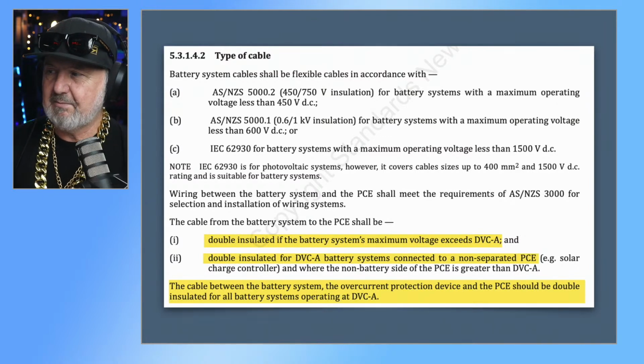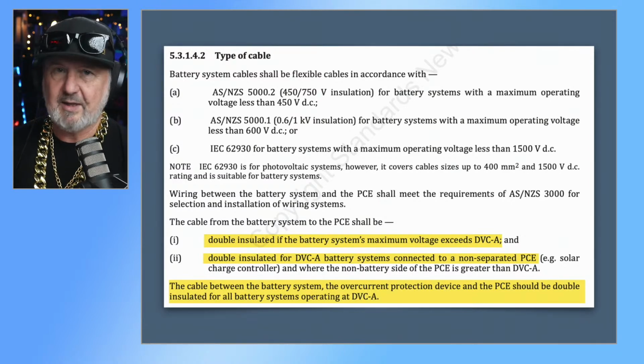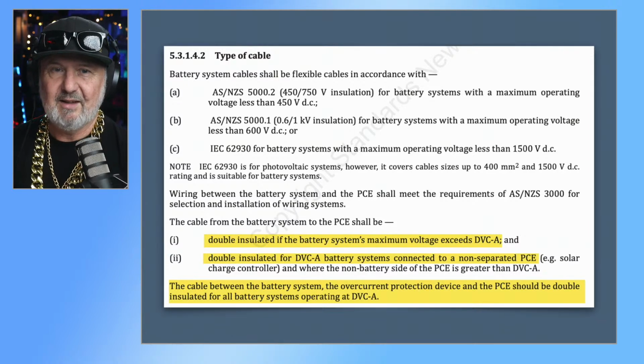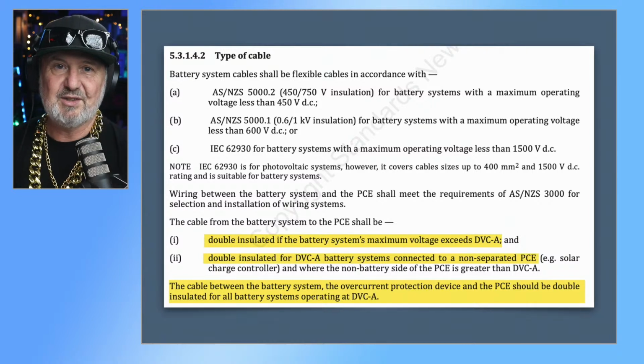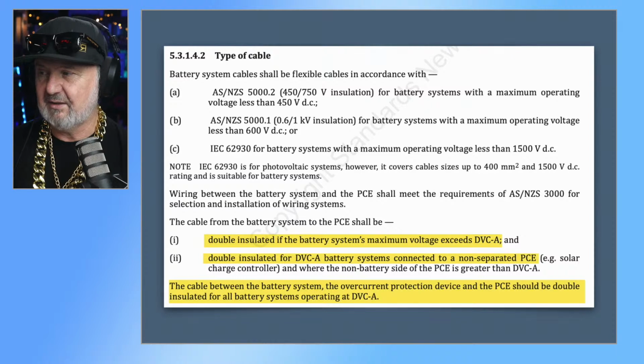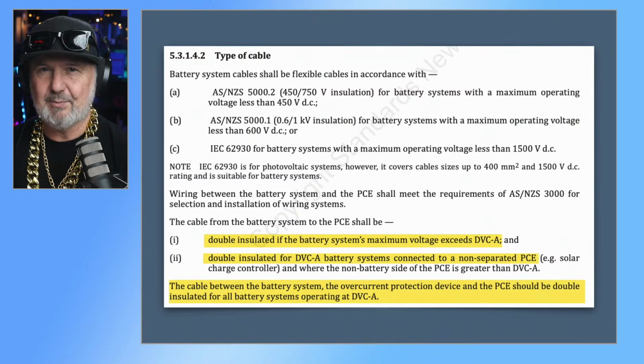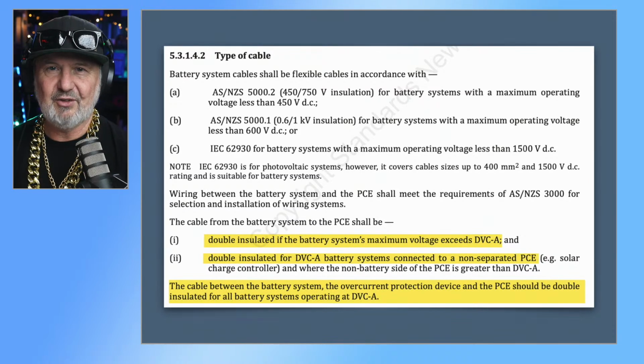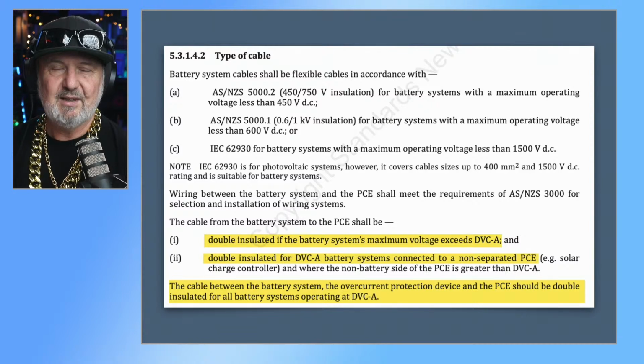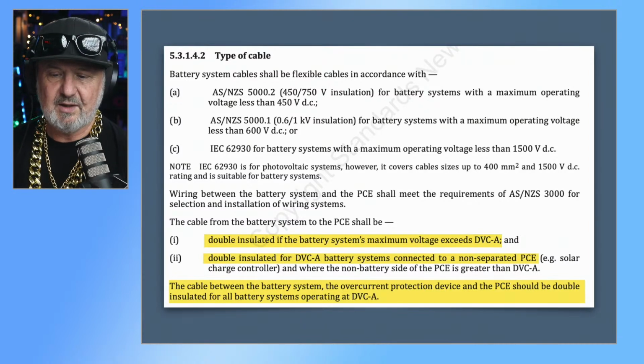And it must be rated for the maximum current rating of the battery system and the short circuit current and duration of the battery system. So under fault condition, before the overcurrent protection device gets a chance to trip, that cable's got to sustain that fault current. And that's the basic premise of cable selection. You would select your overcurrent protection device and then select a cable that is adequately protected by that device.